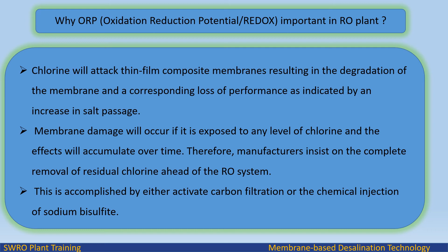Chlorine will attack thin-film composite membranes, resulting in the degradation of the membrane and a corresponding loss of performance as indicated by an increase in salt passage. Membrane damage will occur if it is exposed to any level of chlorine, and the effects will accumulate over time. Therefore, manufacturers insist on the complete removal of residual chlorine ahead of the RO system, accomplished by either activated carbon filtration or the chemical injection of sodium bisulfite.